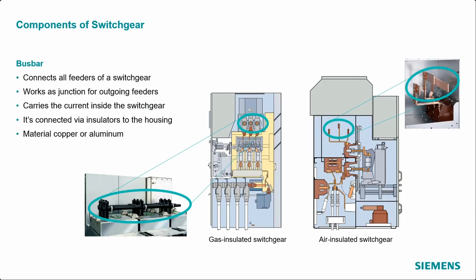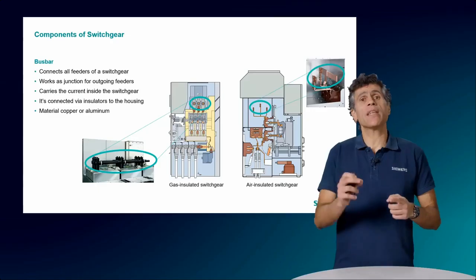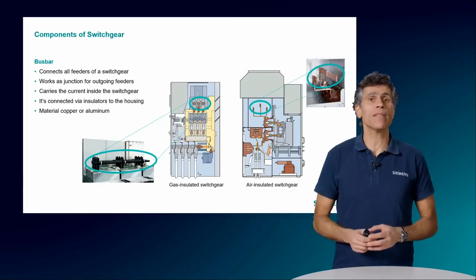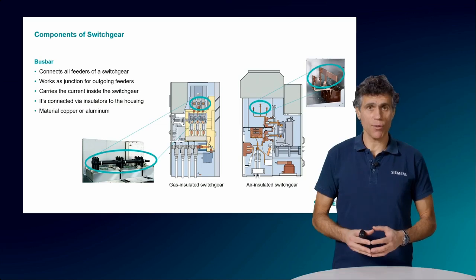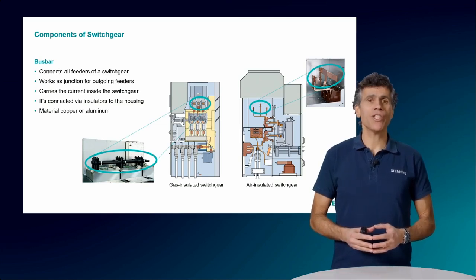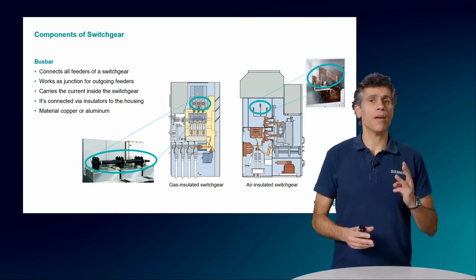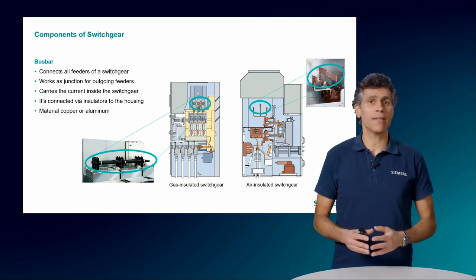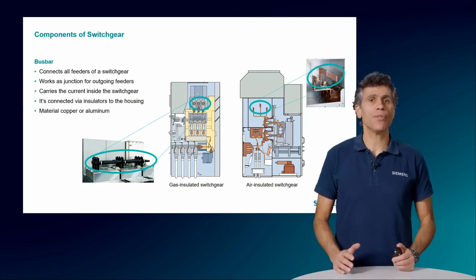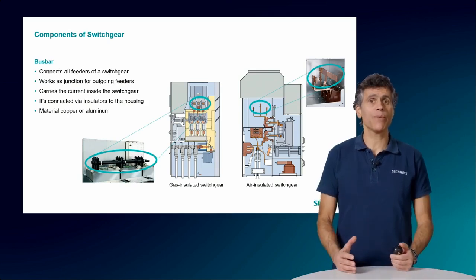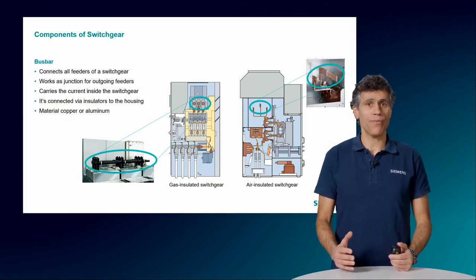It is exactly the same principle as water flowing in a water pipe with many holes or derivations. The water comes inside the pipe and on its way it gets distributed to several openings that go to different places and consumers. But in the switchgear you can see that we have 3 bars, which are called phases, because the electricity is distributed in packs of 3 and therefore we need 3 bars. So usually when we say busbar, we mean 3 phases at the same time.